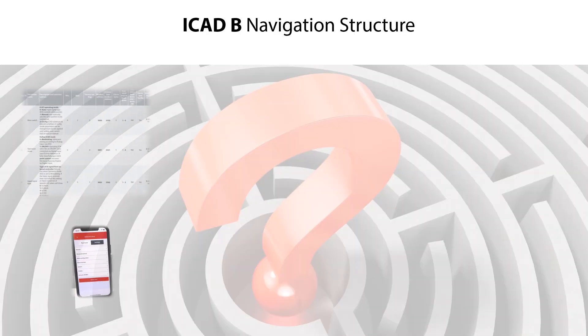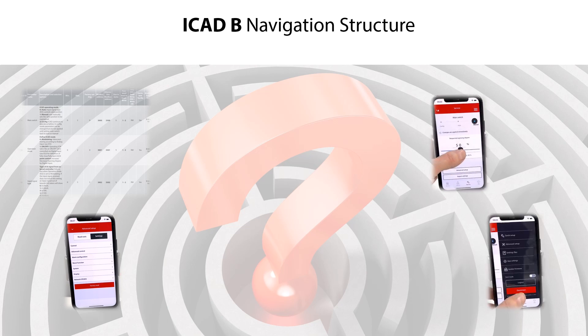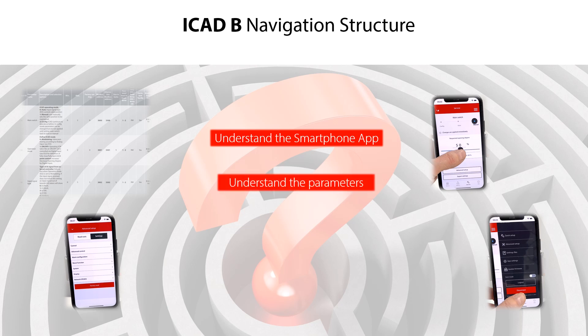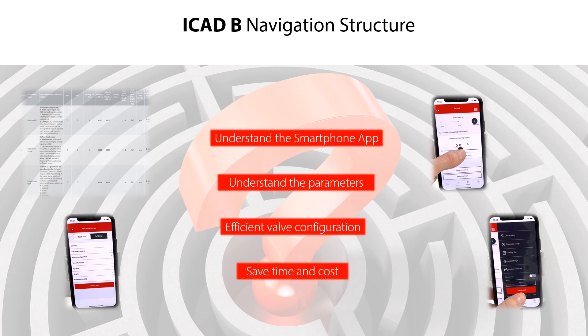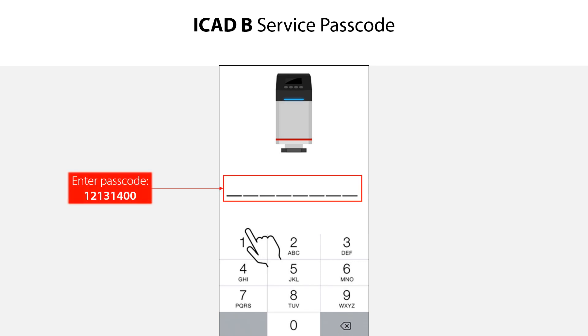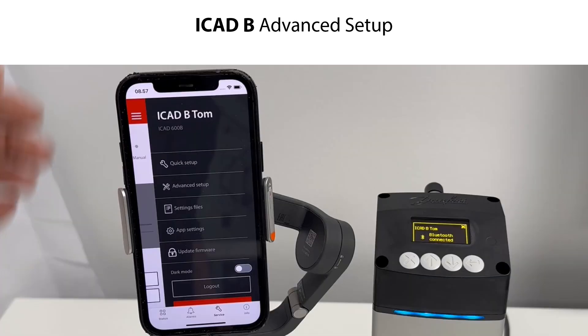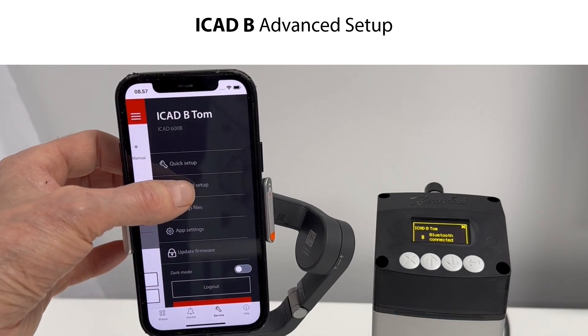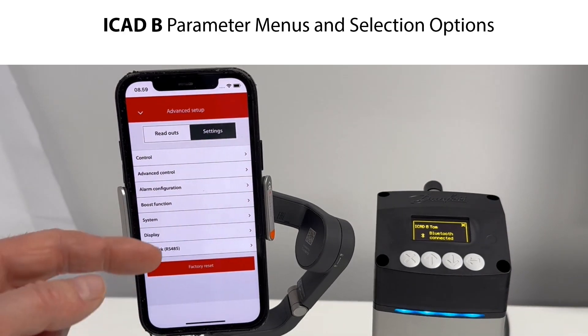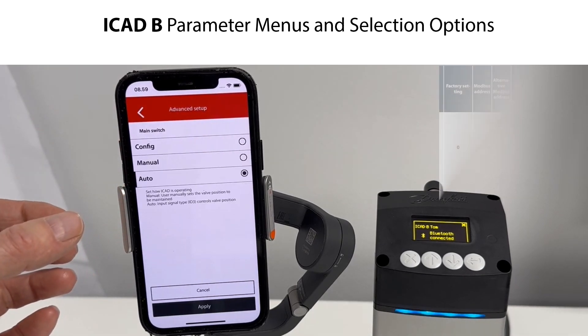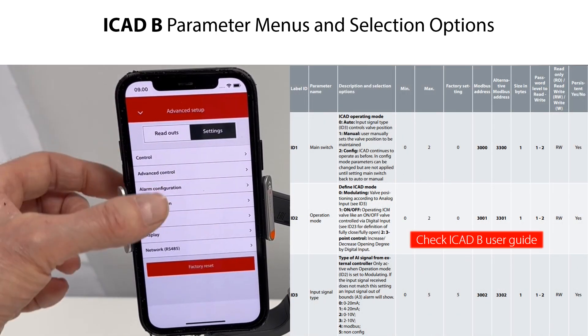Let us demonstrate the ICAD-B and smartphone navigation structure and show you how to do changes to the ICAD-B settings. This will give you a good understanding of how to use the smartphone app and understand the ICAD-B parameters, efficiently supporting valve setup and configuration, saving time and cost. If needed, enter the 8-digit passcode, which from the factory is 12131400. You are now logged in and can do changes to the ICAD-B settings using the advanced setup menu. Press Advanced Setup — you now have access to the control and advanced control parameters, based on the parameter list in the ICAD-B user guide.